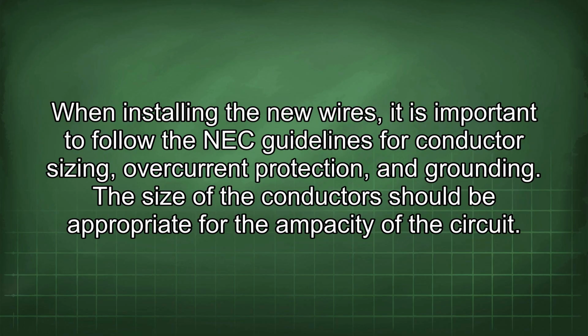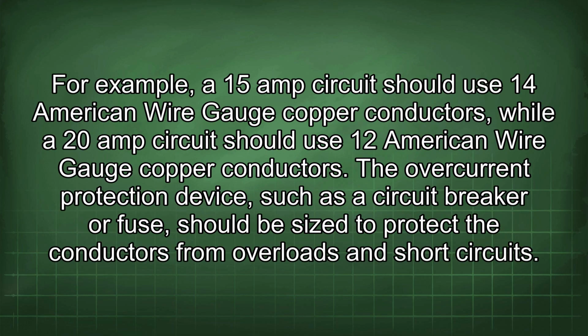When installing the new wires, it is important to follow the NEC guidelines for conductor sizing, overcurrent protection, and grounding. The size of the conductors should be appropriate for the ampacity of the circuit. For example, a 15-amp circuit should use 14 American wire gauge copper conductors, while a 20-amp circuit should use 12 American wire gauge copper conductors.